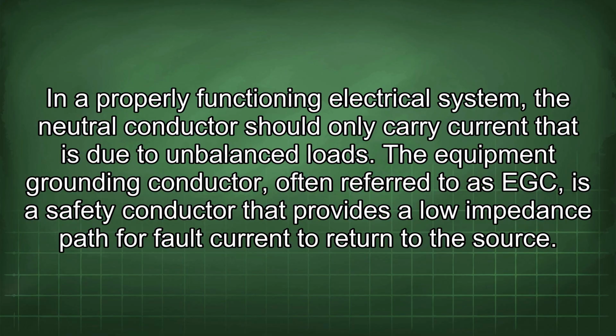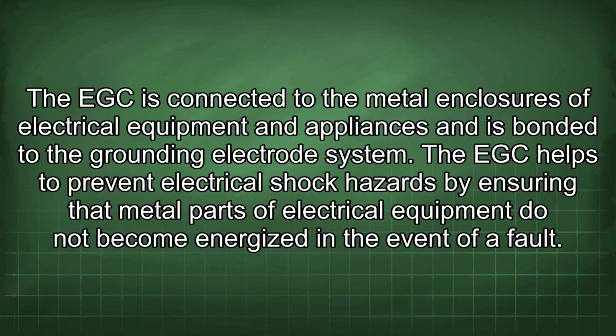The equipment grounding conductor, often referred to as EGC, is a safety conductor that provides a low impedance path for fault current to return to the source. The EGC is connected to the metal enclosures of electrical equipment and appliances and is bonded to the grounding electrode system. The EGC helps to prevent electrical shock hazards by ensuring that metal parts of electrical equipment do not become energized in the event of a fault.